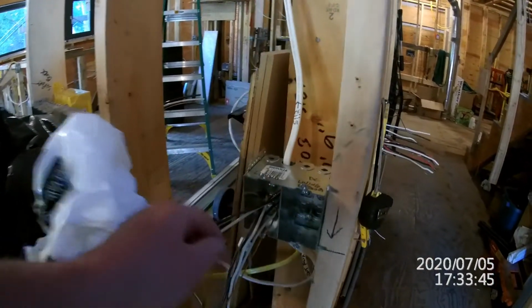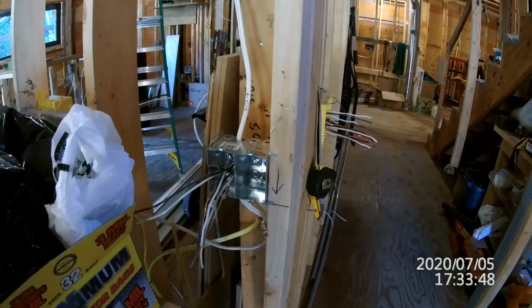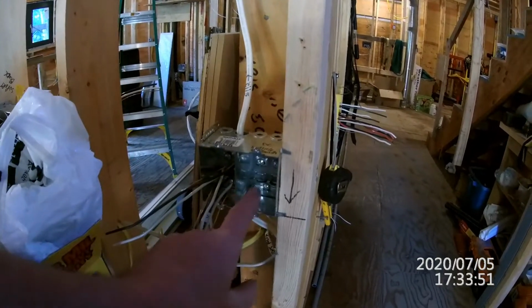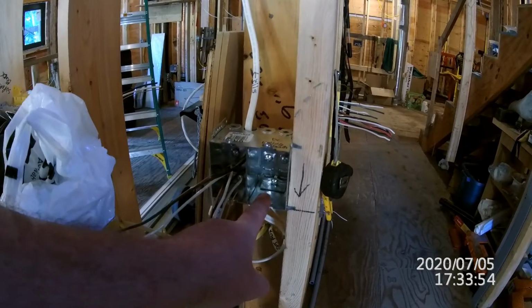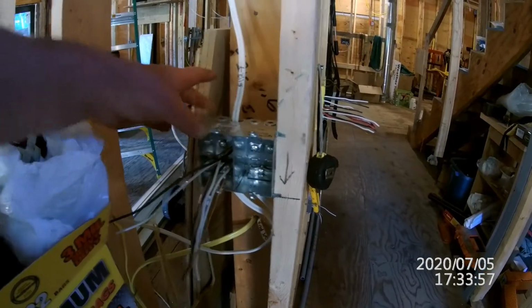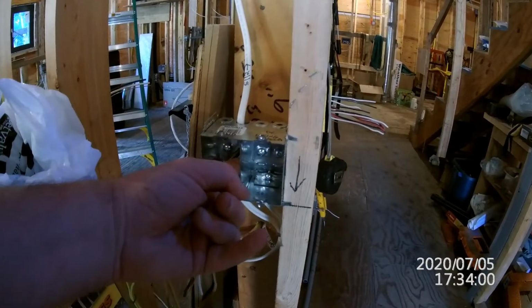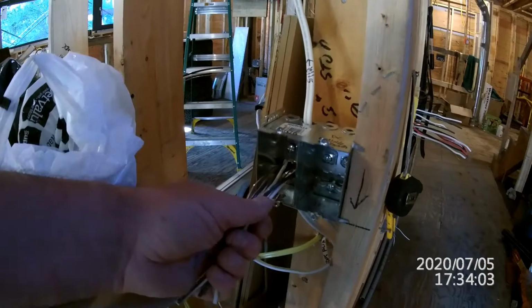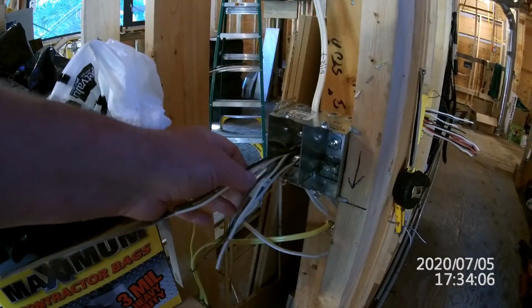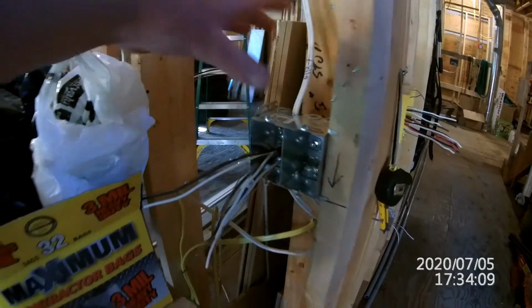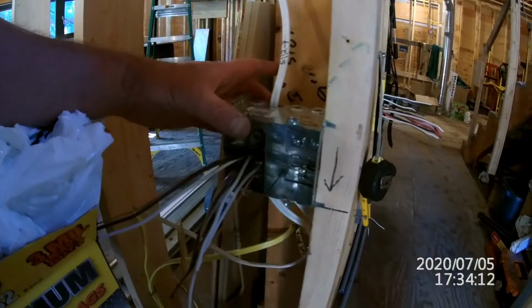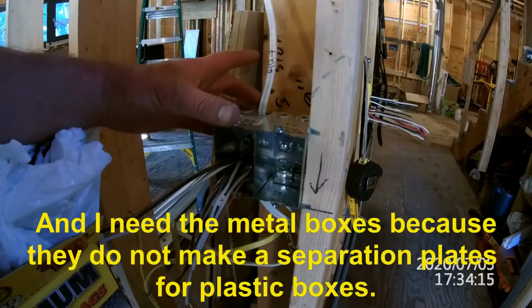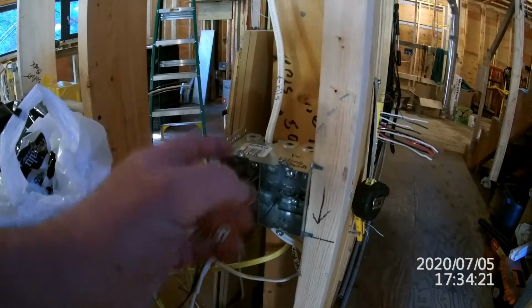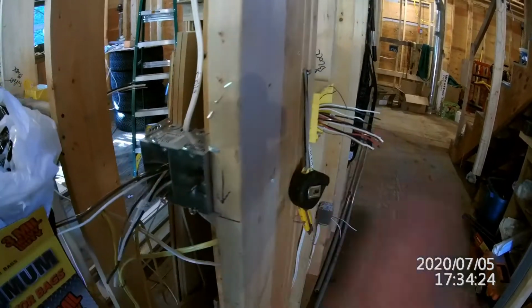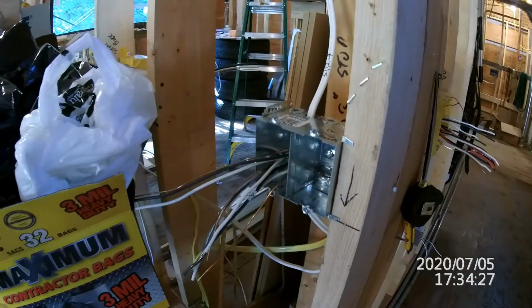The reason this is loose is because step 1, I replaced the 2-gang plastic with this 2.5 inch deep 2-gang metal box and put in this partition plate. But now my box fill on the 110 volt is too high for a single 2.5 inch box. So now I'm going to have to step it to a 3 inch deep box, and they only come in gangable boxes, meaning it's a single gang that you have to take a partition plate out of and keep joining up if you need multiple gang boxes.